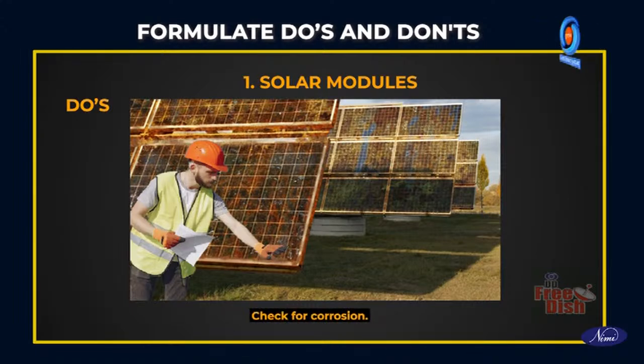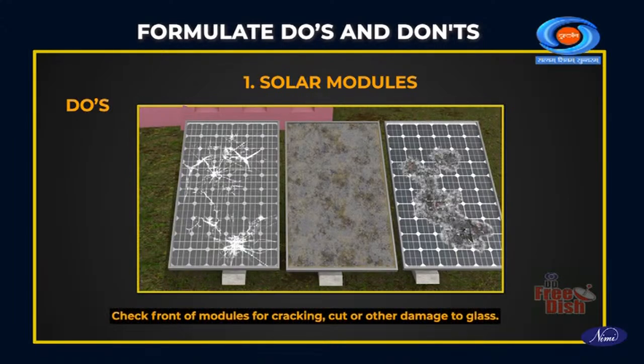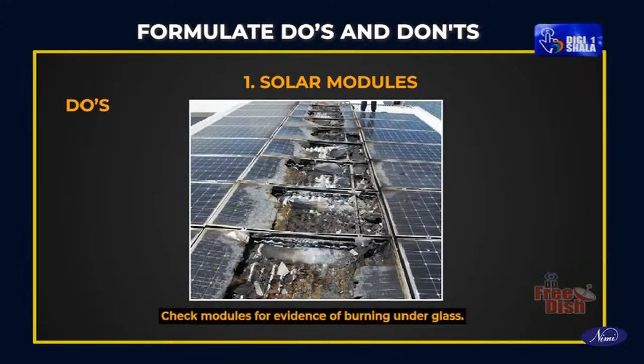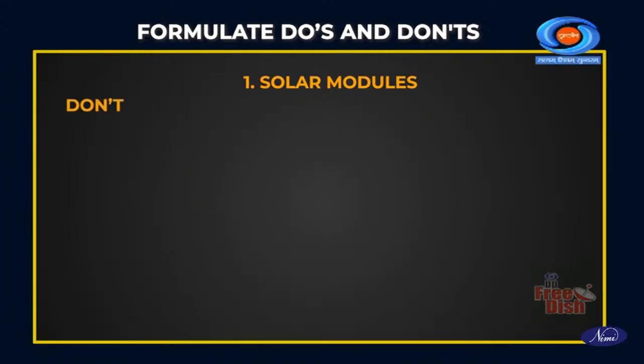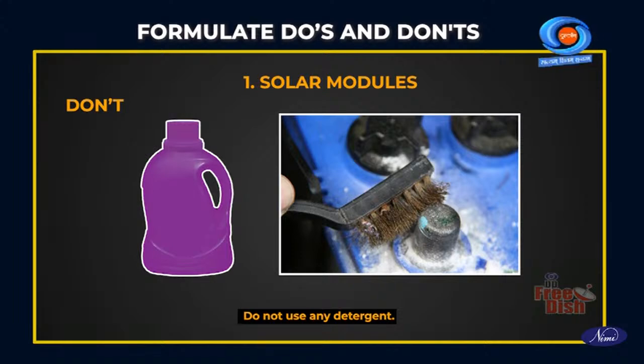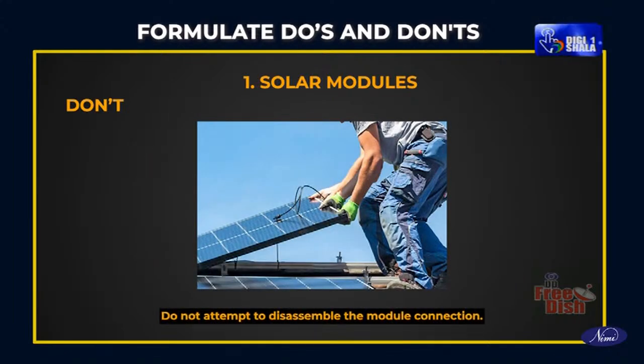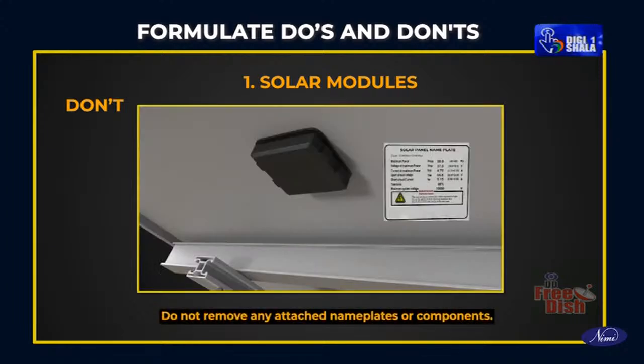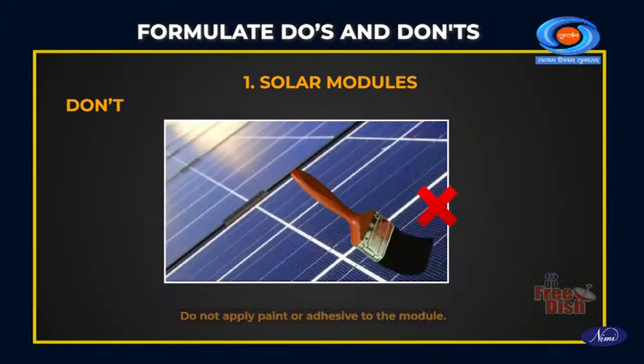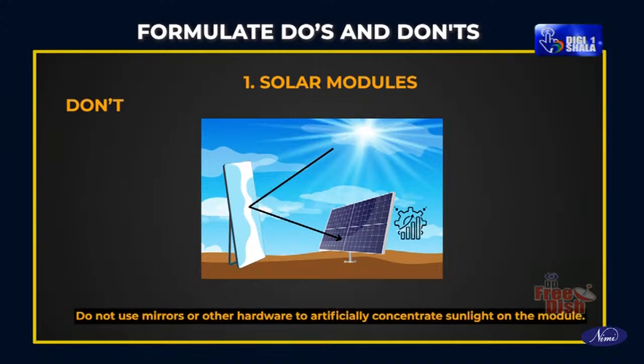Check for corrosion. Check the front of modules for cracking, cuts or other damage to the glass. Check modules for evidence of burning under the glass. Don'ts: Do not use any detergent. Do not attempt to disassemble the module connection. Do not remove any attached nameplates or components. Do not apply paints or adhesive to the module. Do not use mirrors or other hardware to artificially concentrate sunlight on the module.